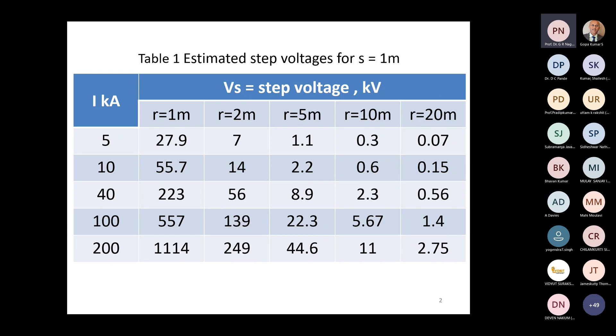Otherwise, it can be very dangerous for two reasons. One is contact potential, which is very high, and huge currents can be driven through the human body or the animal body. And if the person is in the proximity also, there can be very dangerous potentials across each step, and it can vary from a few tens of kilovolts to even several hundreds of kilovolts at short distances, and comes down very significantly with distance. A radial distance of 10 meters may be considered reasonably safe, whereas a distance of 20 meters and beyond will be quite safe.